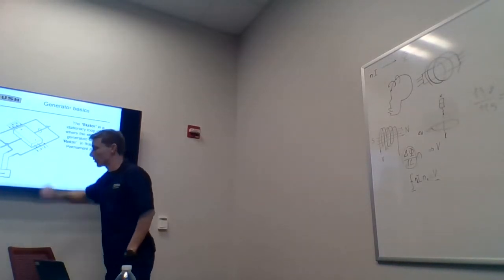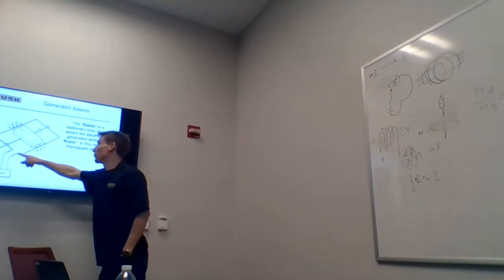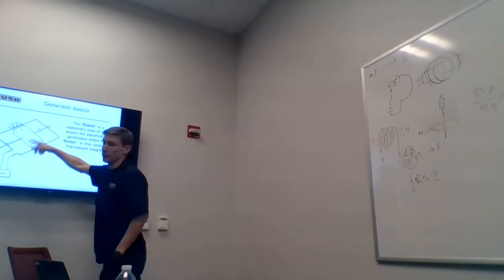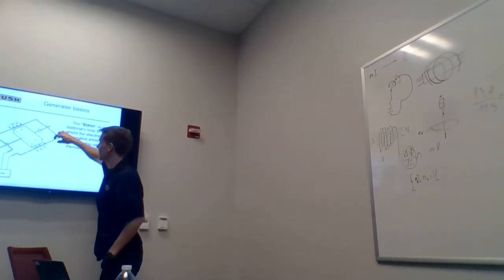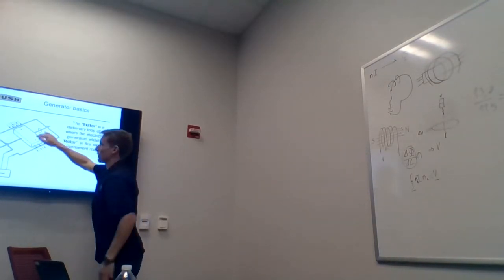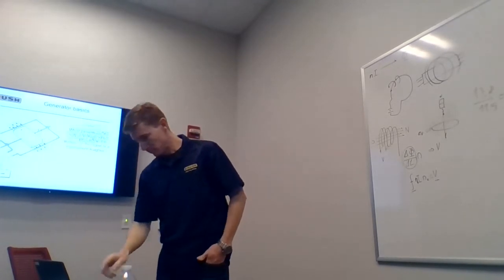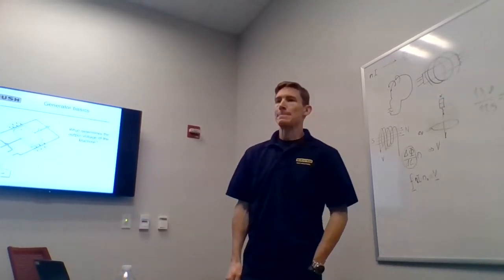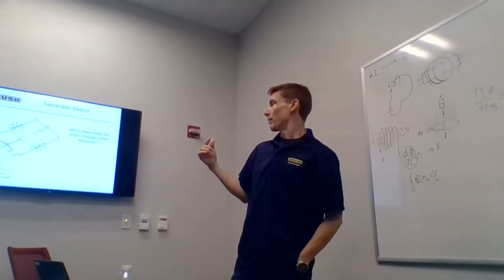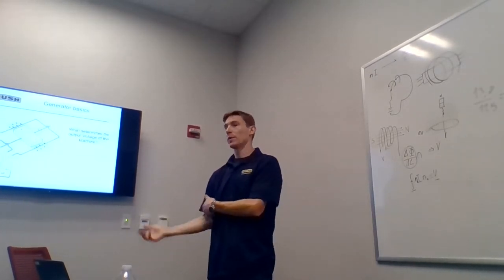You need to know there will be difficulties in placing turns around the shaft, and they can't all be in the same place — the spacing is really important. So when you add turns, you have to distribute them. Adding more turns will get you more voltage, but you're also adding resistance, which creates more heat that you need to get rid of. That's part of the design.